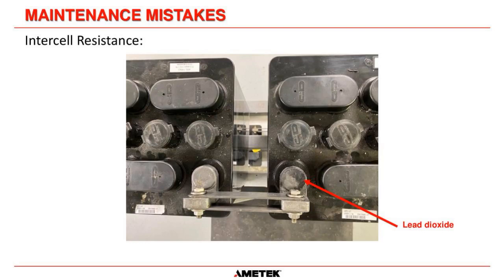The biggest mistake we get is people don't quite understand what you're actually measuring. What you need to do is put a probe on the actual lead post here and a probe on this lead post here. You're actually measuring the connection resistance between this post and the bus bar, then the bus bar itself, and then through the connection, back onto this post here.